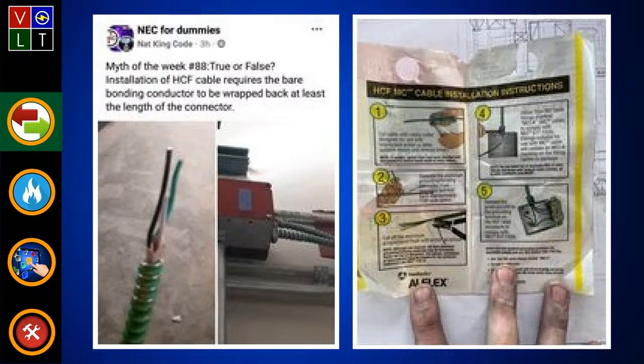And then over here is the actual manufacturer instructions for the cable that's in the picture on the left, which is HCF. I can't remember the exact part number, but it basically shows you right there, take your dikes, just cut it off and slide your connector on. So at some point, somebody must have taken an energized conductor and touched it to the jacket, and the overcurrent device didn't open. So they said, well, we need to reduce the impedance of this fault path.